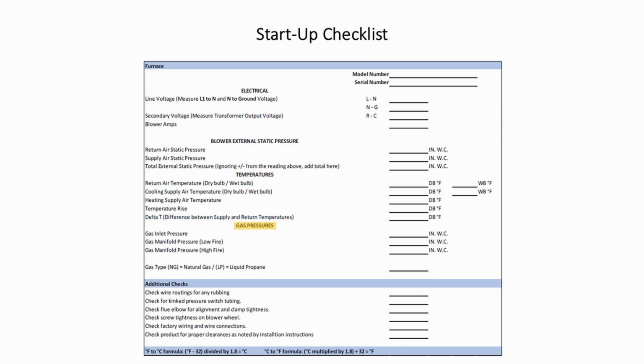Under the gas pressure section, please record the gas inlet pressure in inches of water column, the gas manifold pressure during low fire operation in inches of water column, gas manifold pressure during high fire operation in inches of water column. Then record the gas type, natural gas or LP.